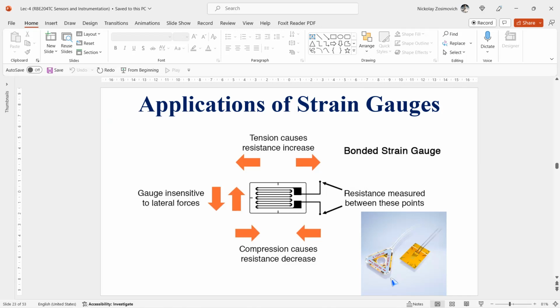There are two ways strain gauges are applied in practice. First, mounted directly on the object whose strain and stress behavior has to be measured. When cemented properly, the strain of the object is transferred ideally to the strain gauge. For instance, to measure the bending of a robot arm. And second, mounted on a specially designed spring element, like a bar, or ring, or yoke, to which the force to be measured can be applied. For instance, to measure stress in driving cables and gyros.